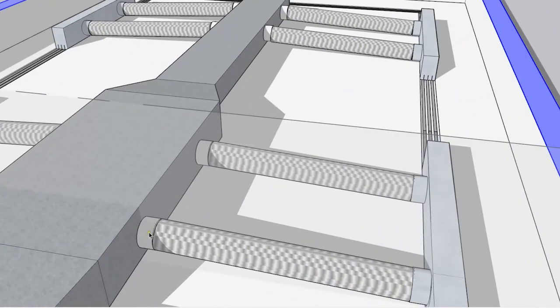If you want the air to spread evenly, you can use a balancing damper (BD). BD is a balancing damper. If you want to adjust the flow rate in proportion, you can use the balancing damper. You can adjust the flow rate at the first opening, then adjust the flow rate at the second opening, to maintain the same amount of airflow throughout.